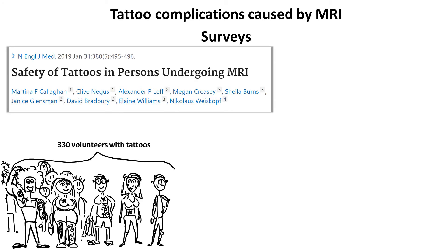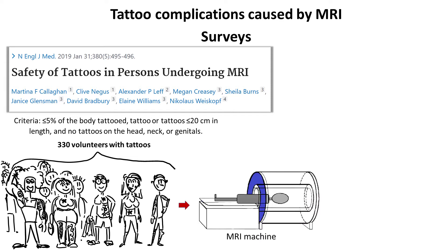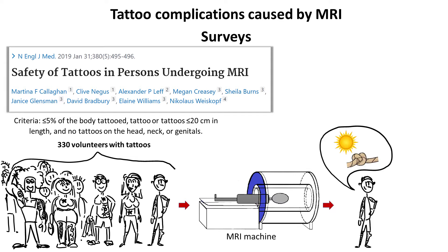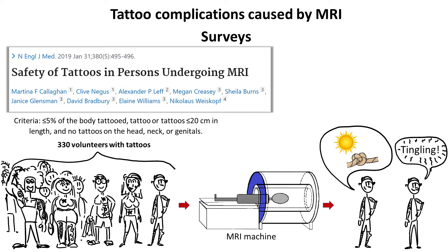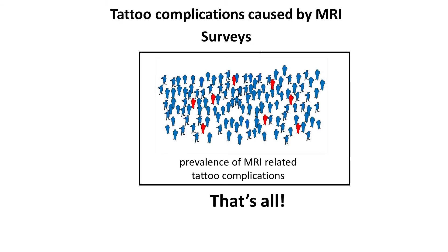The second research studied 330 volunteers with tattoos that had to satisfy certain criteria — for instance, they had to cover less than 5% of body area. One person reported a tight and warm feeling in the tattooed area, classified as an adverse reaction, and another person retrospectively reported awareness of a tattoo and tingling when scanning began, which was not classified as an adverse reaction. This research estimated the probability of a tattoo adverse reaction due to MRI scan at 0.17%.